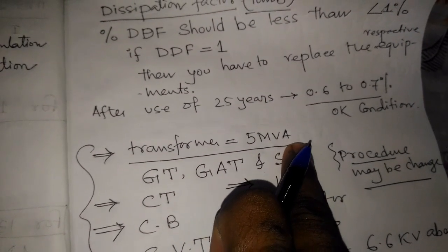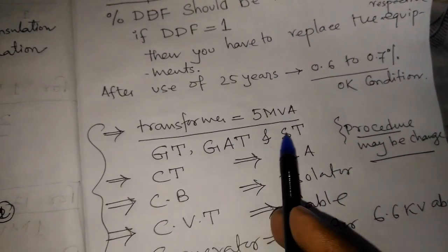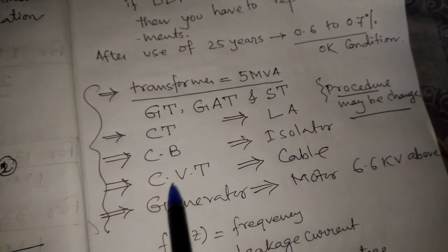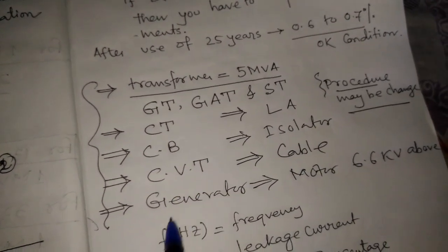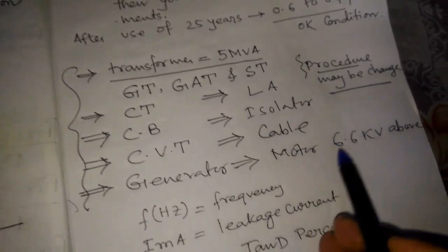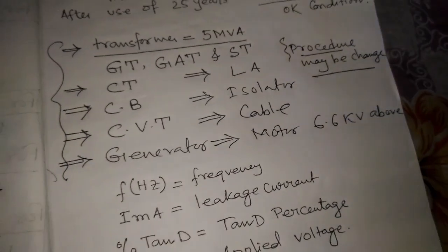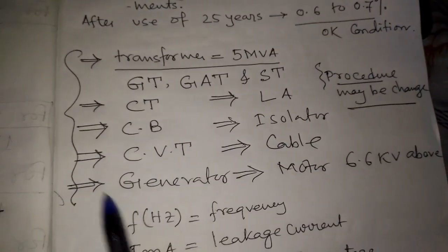For transformers above 5 MVA we perform the Tan Delta test. We do the Tan Delta test on GT, GAT, ST, CT (current transformers), circuit breakers, CVT (capacitive voltage transformers), generators, lightning arresters, isolators, cables, and motors with a rating greater than 6.6 kV. The procedures of the testing may change accordingly.